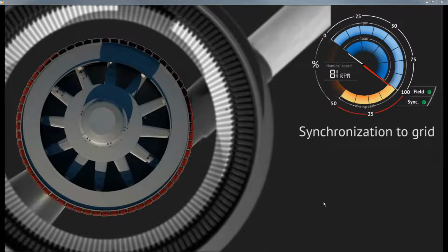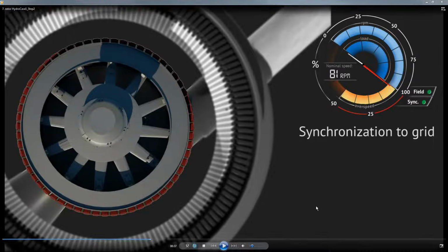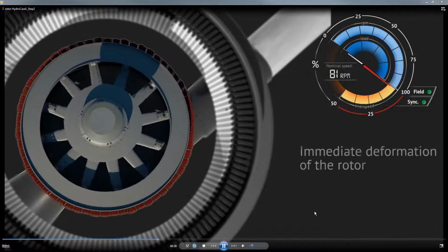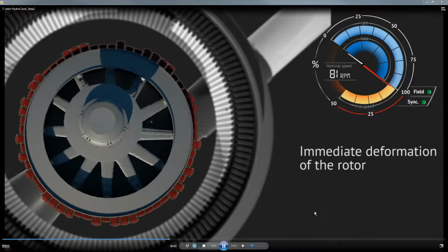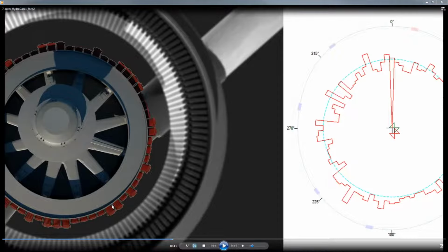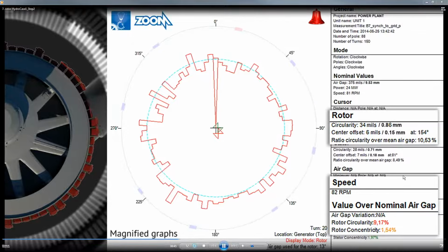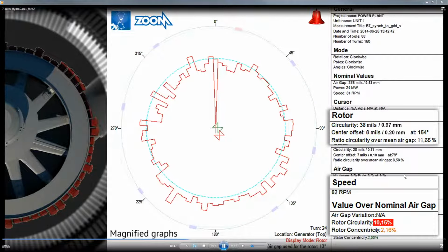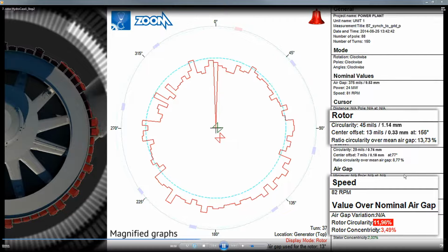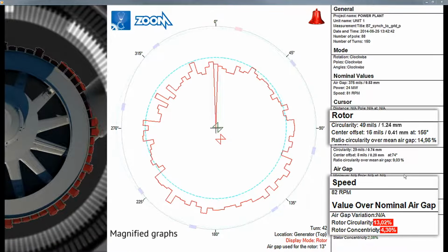So when they introduced very strong opposing forces to what the rotor was providing, coming from the stator, it had a significant impact. Let me just show you, if you look at the rotor poles all the way around, you'll notice that when they synchronized, there was a serious issue. So you can see not only did the poles come out, but the rotor actually shifted position. I had never seen that before. And this is a slow representation. You can see how the rotor shape changed significantly and actually moved downstream.